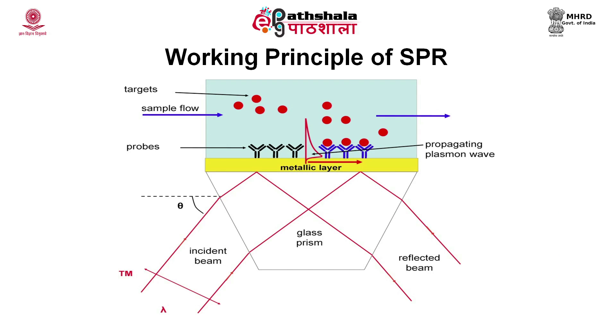Next, we will discuss the working principle of SPR. SPR stands for surface plasmon resonance, in which a metal plate is used as the platform for the immobilization of the biocomponent. Light is guided at the platform of the metal and is reflected at a certain angle. The presence of biological entities at the surface of the platform changes the resonance angle or the intensity of the reflected light, which is measured as the detection signal.